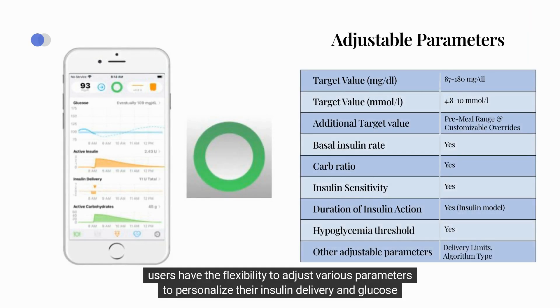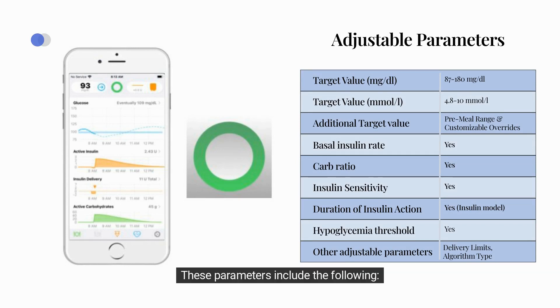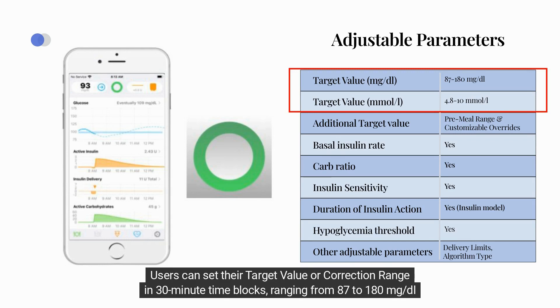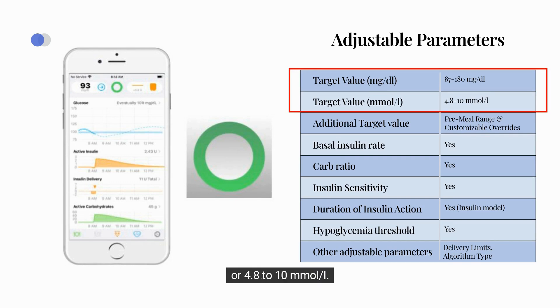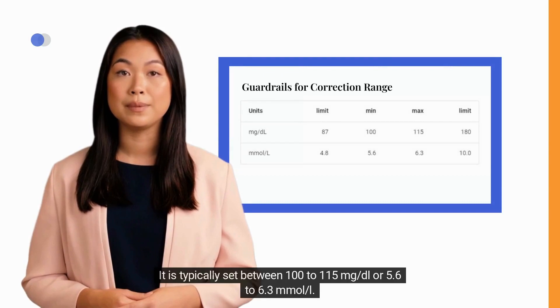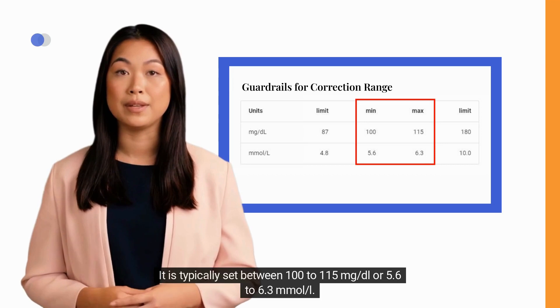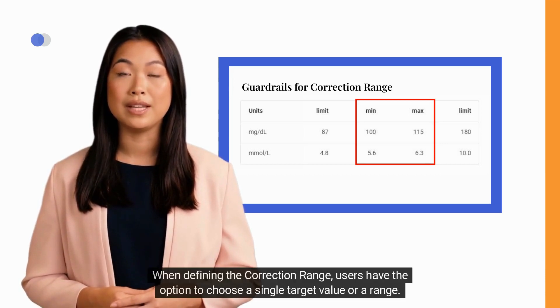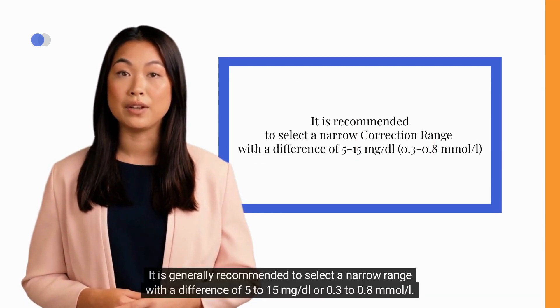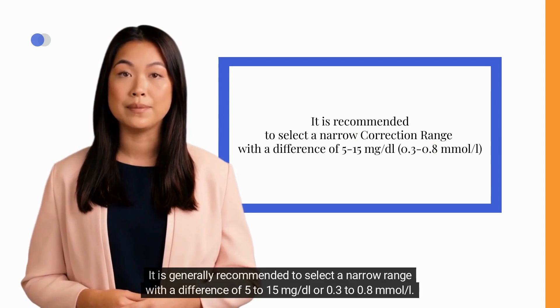Users have the flexibility to adjust various parameters to personalize their insulin delivery and glucose management. Users can set their target value or correction range in 30-minute time blocks, ranging from 87 to 180 mg/dL or 4.8 to 10 mmol/L, typically set between 100 to 115 mg/dL or 5.6 to 6.3 mmol/L. When defining the correction range, users can choose a single target value or a range, with a recommended narrow difference of 5 to 15 mg/dL or 0.3 to 0.8 mmol/L.